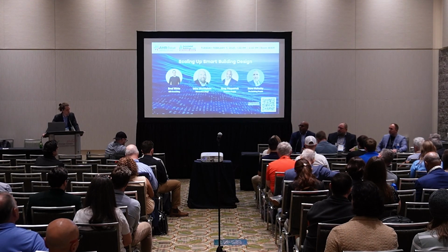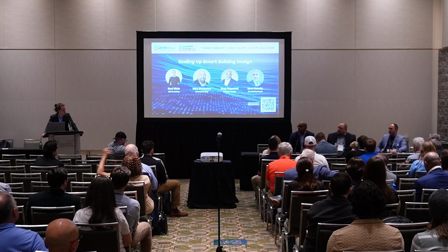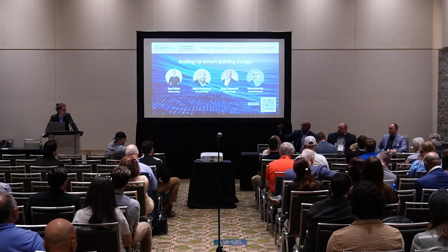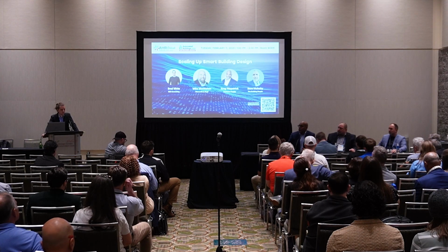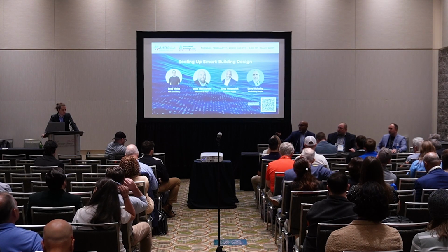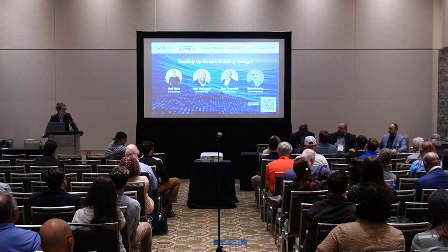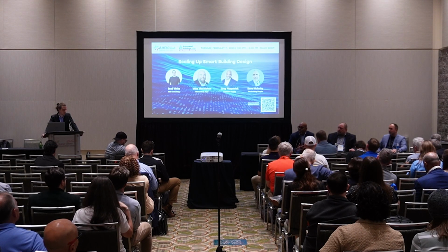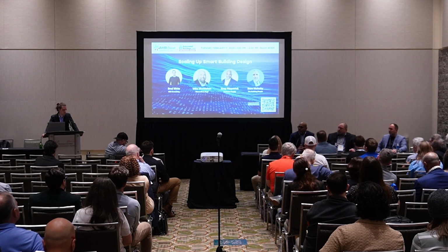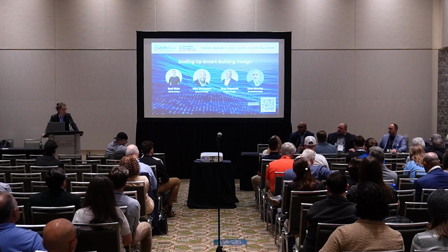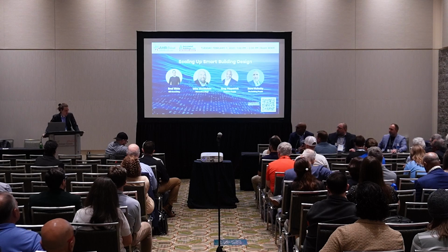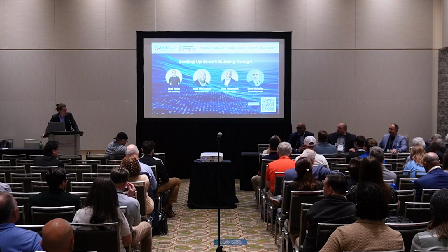So where are my routers? Where are my network management switches? Where are my edge switches if I have IP technology? How much technology is IP? How much is 485? Am I using some type of wireless BACnet solution? All of those things can go on one drawing, and that's what we've been trying to do, promote the use of these types of documents so that we can have a set of clear and concise documents so that we can get the appropriate bidders. You mean we shouldn't just leave it to the contractor to figure all that out? Absolutely not.